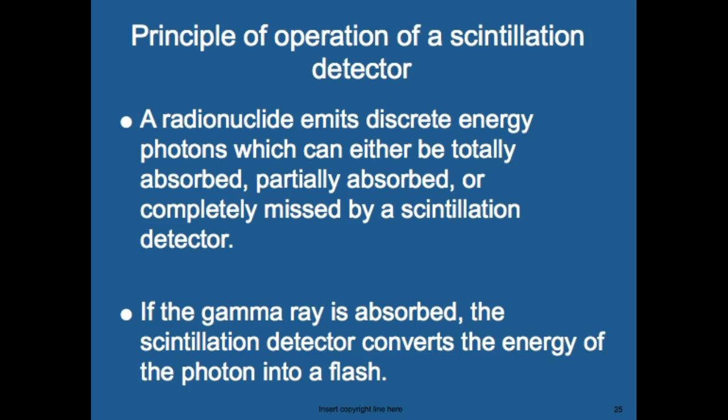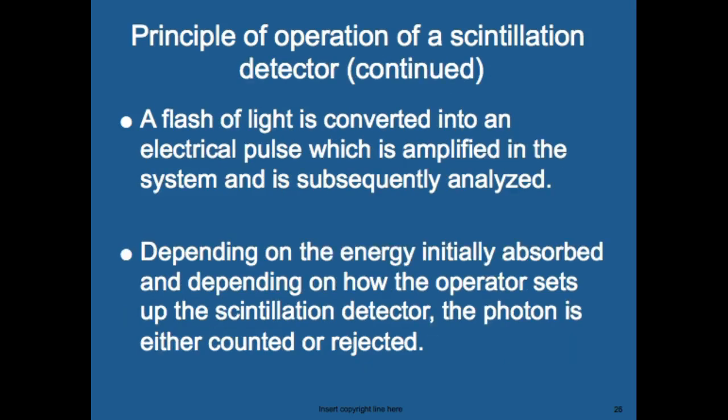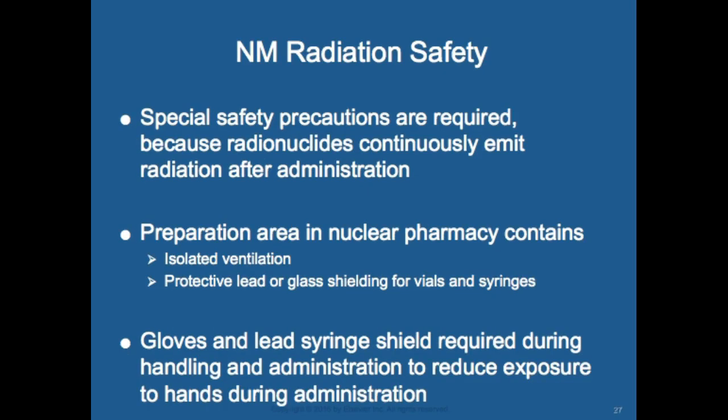The principle of operation of a scintillation detector: a radionuclide emits discrete energy photons which can be totally absorbed, partially absorbed, or completely missed by the detector. If a gamma ray is absorbed, the scintillation detector converts the energy into a flash of light, which is converted into an electronic pulse and amplified. Depending on the energy of the initial absorbed photon and how the operator sets up the detector, the photon is either counted or rejected.